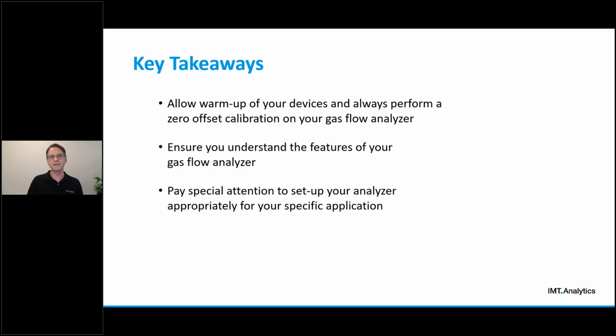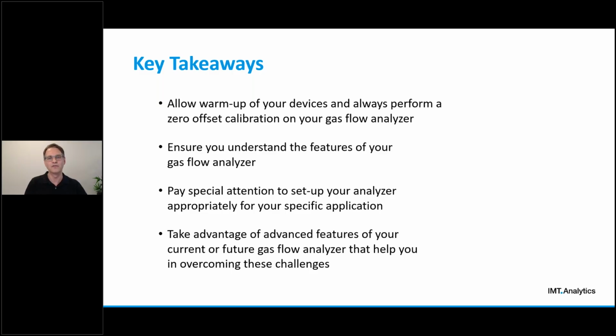And if there's one key takeaway that I want you to keep from this session, then it's the gas standard. Set the gas standard same as on your device under test. That's really most important. And last but not least, take advantage of advanced features that your current or future gas flow analyzer can offer to reduce the risk of measurement and reading errors.